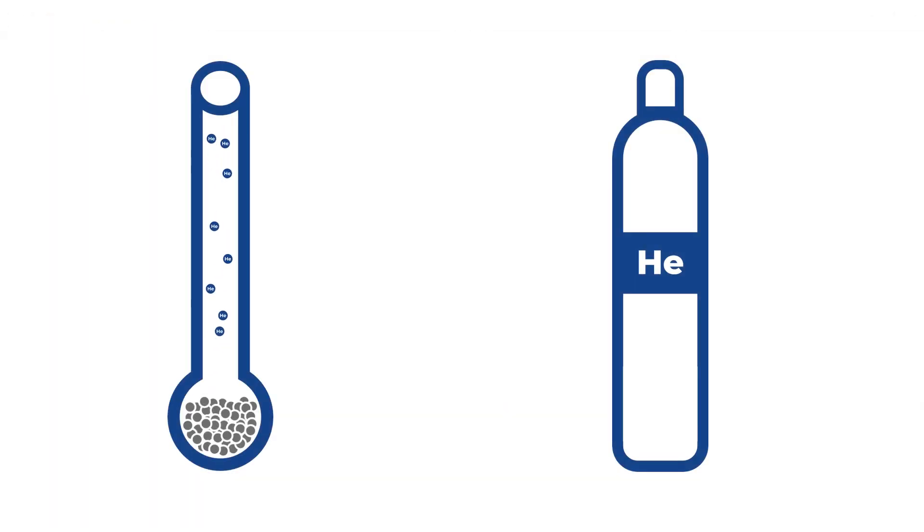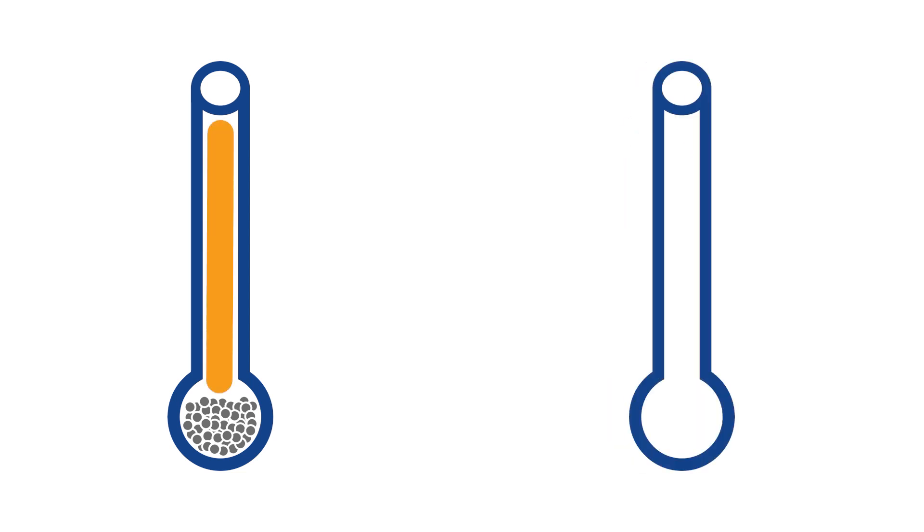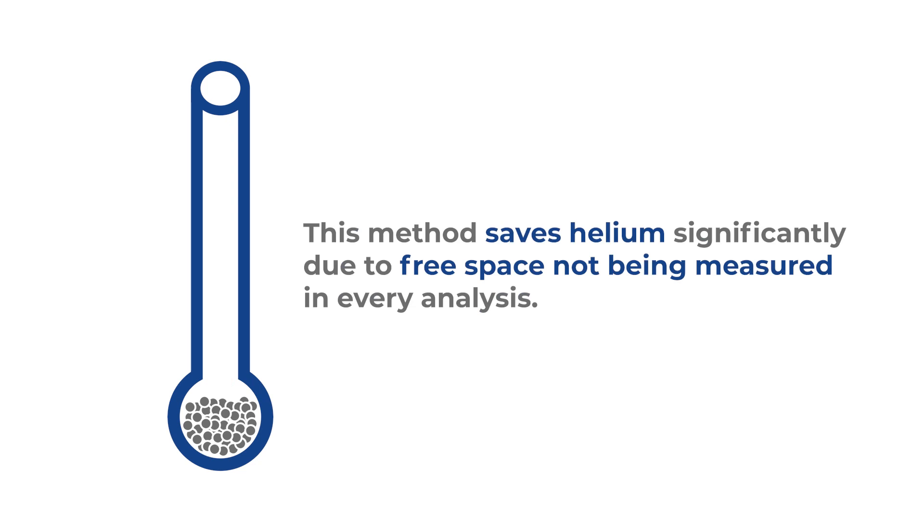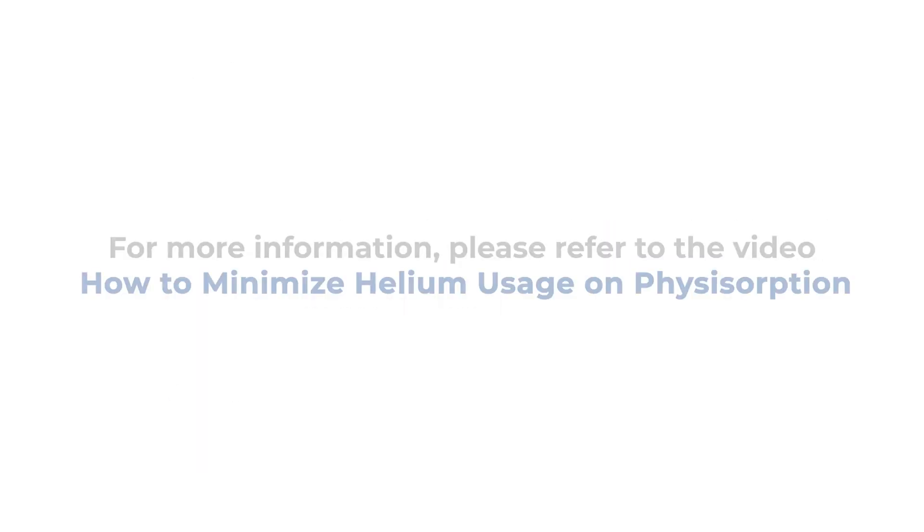Another way to avoid helium exposure on a sample is calculating free space with a calibrated blank tube and density of the sample. It also helps to save helium significantly since the free space is not being measured in every analysis. For step-by-step instructions on this method, please refer to how to minimize helium usage on physisorption instruments video.